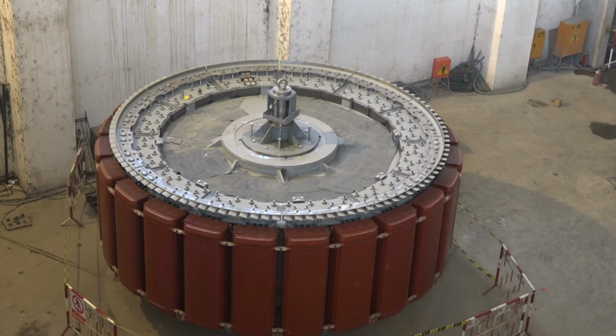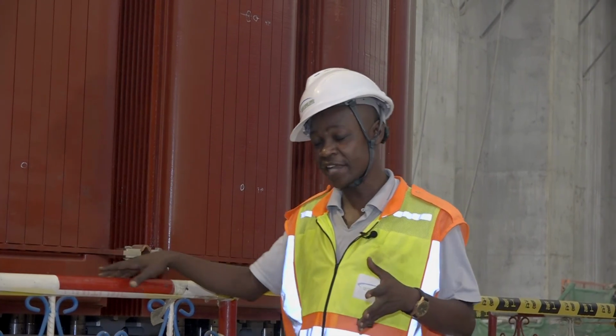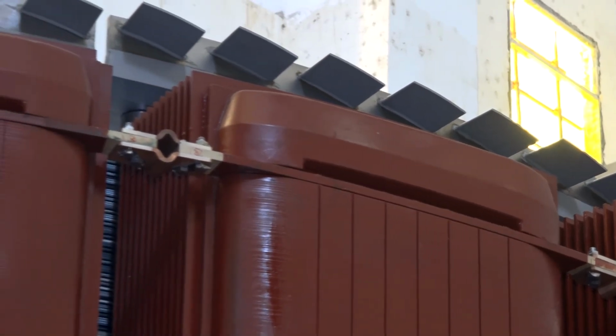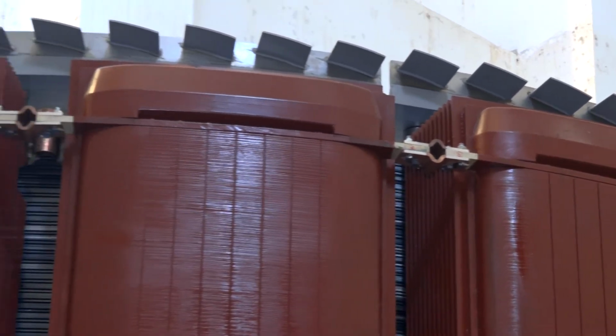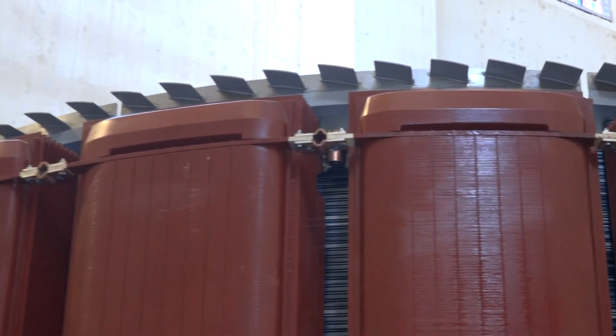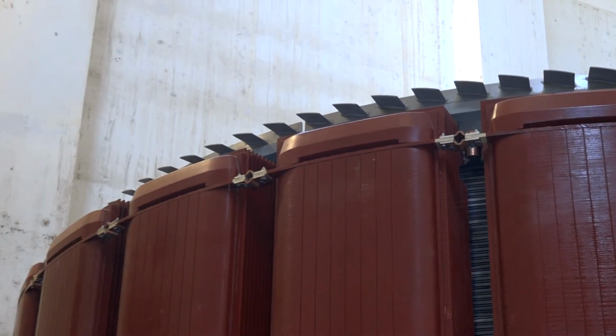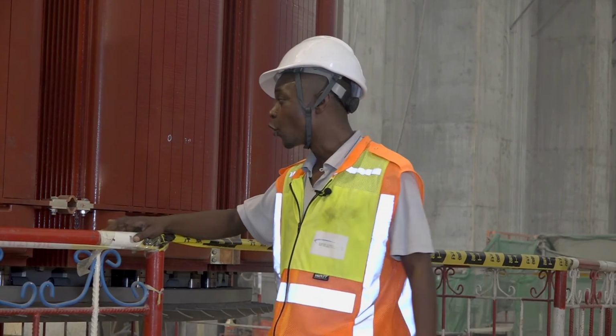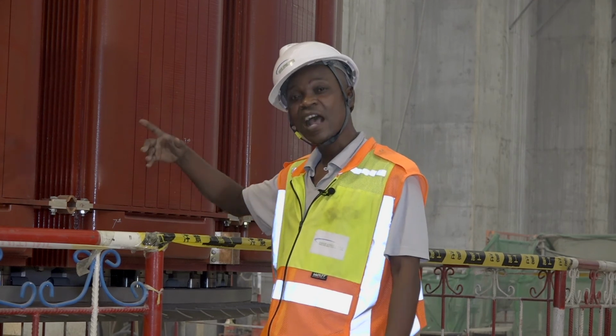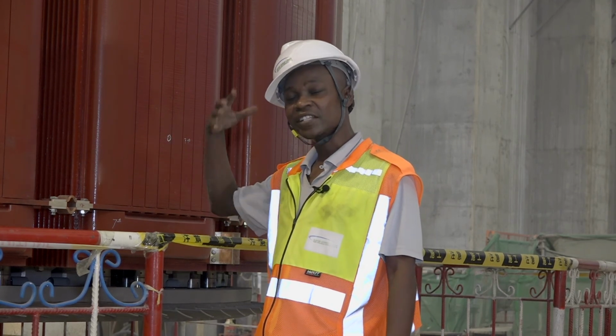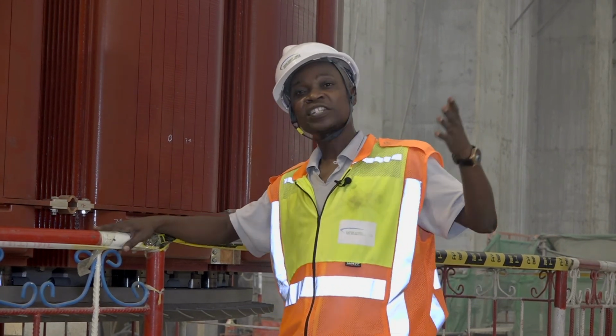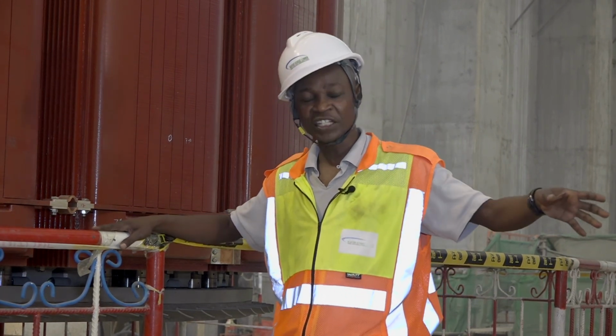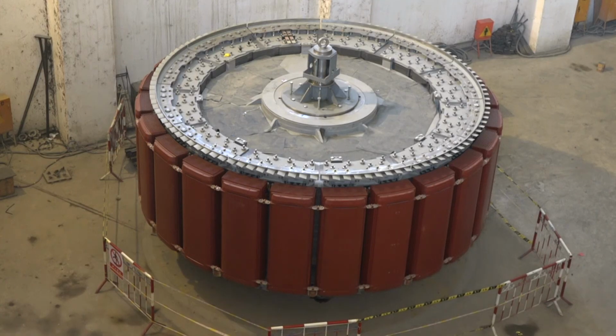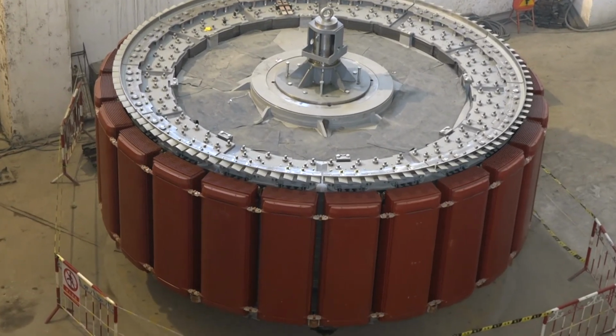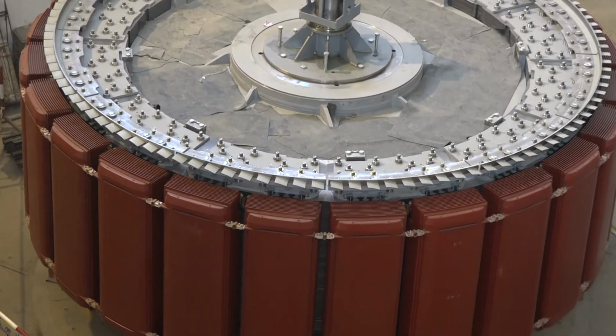This is the rotor, or the rotating part of the generator. As the turbine spins, it will be rotating the rotor. And in the rotor we inject a direct current. And that direct current will create a magnetic flux around the conductors. And it is that flux which, when it interfaces with the stator windings, we induce a voltage in the stator. But our main concern is the rotor construction which has taken place. This rotor assembly has already been completed.